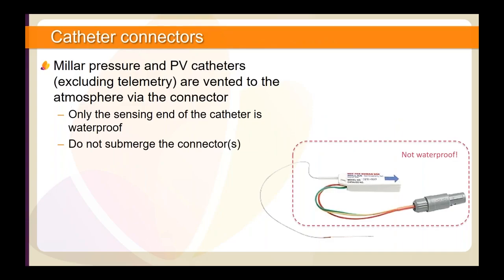Millar pressure catheters and our pressure volume or PV catheters are vented to atmosphere via the connector. Only the sensing end of the catheter is designed to be implanted and is therefore waterproof. It is important that the connectors are kept clean and dry. They can be wiped clean with a damp cloth or gauze if needed, but should never be submerged in water.